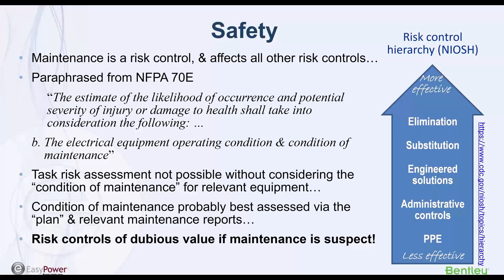The impact of administrative controls, such as the use of an ERMS setting, i.e. the maintenance setting on a circuit breaker or relay or whatever else, will also depend on that maintenance. Even your PPE itself needs maintenance. The reality is that maintenance is just critical to safety and reliability, and there's very little one can do to get around that.